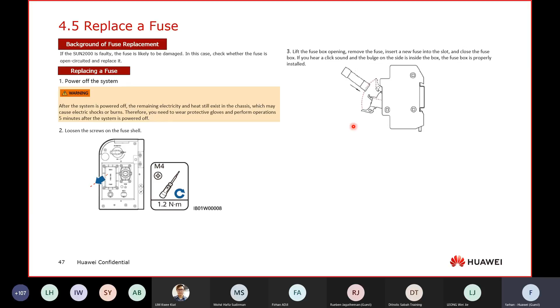To replace the fuse, first shut down the system following the guideline on how to shut down the inverter, then turn off the battery using the DC switch for the power module. Downside there's a cover you can remove to open and find the fuse, then replace it. It's a normal fuse, and inside the package we provide spare fuses — I think 2.